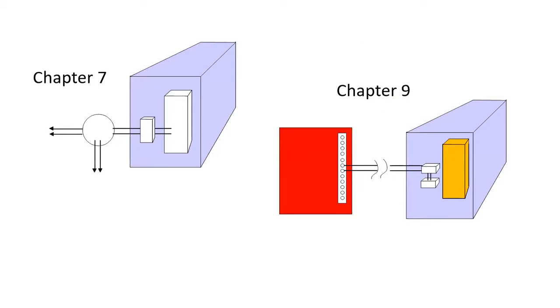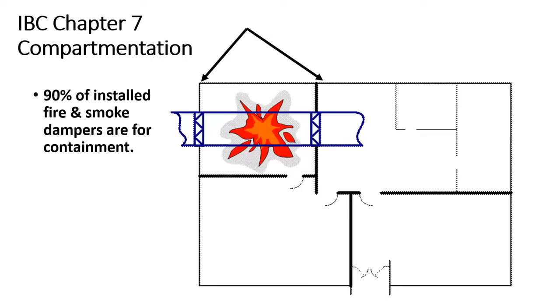Next. So Chapter 7 dampers are standalone dampers. The actuator and damper themselves are not connected to the firefighter's smoke control panel or to the fire alarm panel. The smoke detector is wired to the fire alarm panel. So on the left side, Chapter 7, the damper stands alone with the smoke detector. Chapter 9 dampers, which is smoke control, are going to be connected centrally, either to fire alarm or to the smoke control portion of it, a UUKL panel. And it's important to remember those distinctions because those determine your testing requirements also. With Chapter 7 every 4 years, Chapter 9 once or twice a year. And that is confused in engineers' specifications for the dampers, particularly for the switches.